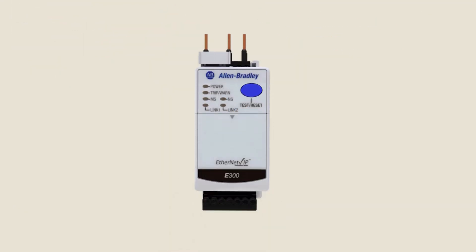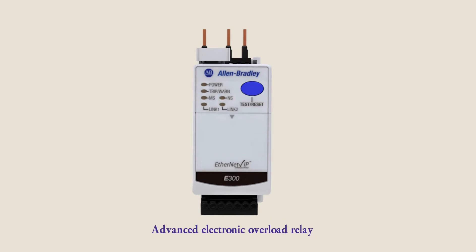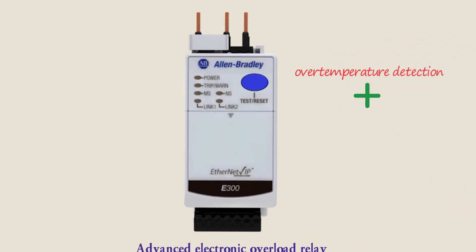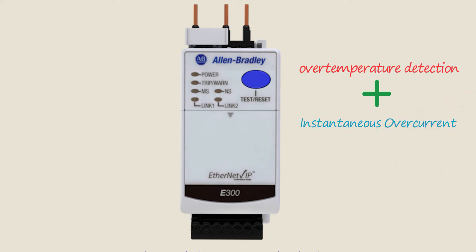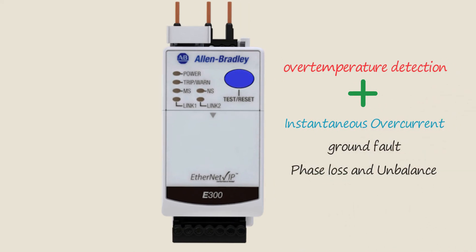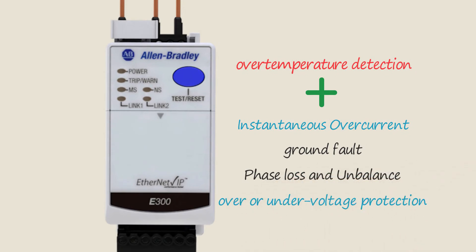Advanced electronic overload relays offer other functions in addition to over-temperature detection, including instantaneous over-current, ground fault, phase loss and imbalance, plus over or under voltage protection and more.